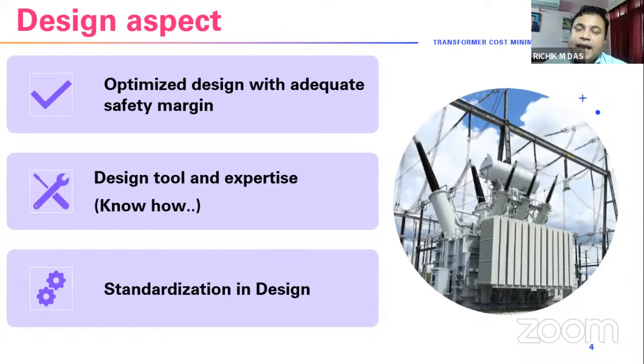Then design tools and expertise. In today's scenario, transformer ratings are increasing day by day, so we need good design tools that can accurately calculate the various conditions — dielectric conditions, thermal conditions, and mechanical integrity. All three major things we have to check through the design tool. Now we have state-of-the-art design tools from so many manufacturers that can calculate very precisely the different conditions of the transformer and check the adequate safety margin in all aspects.